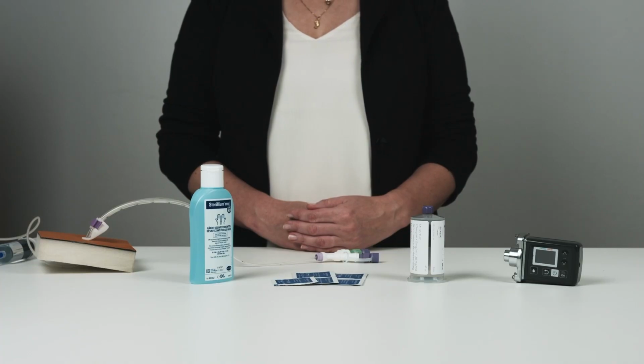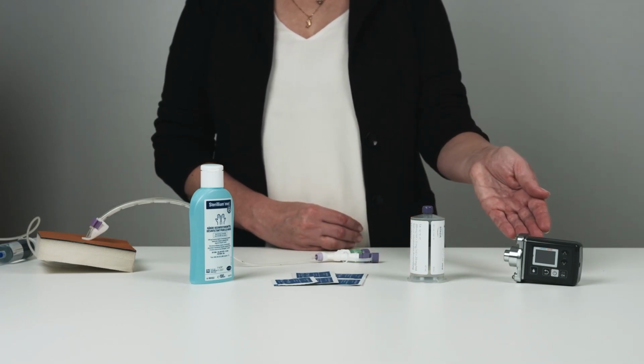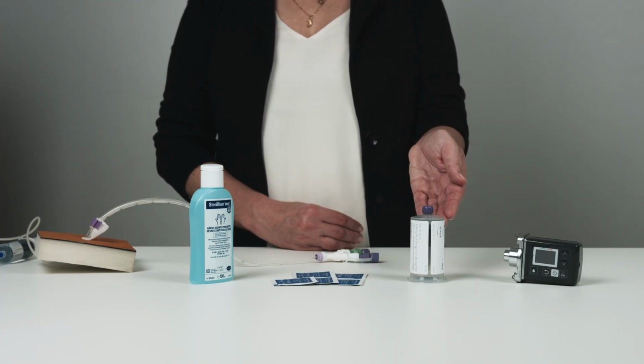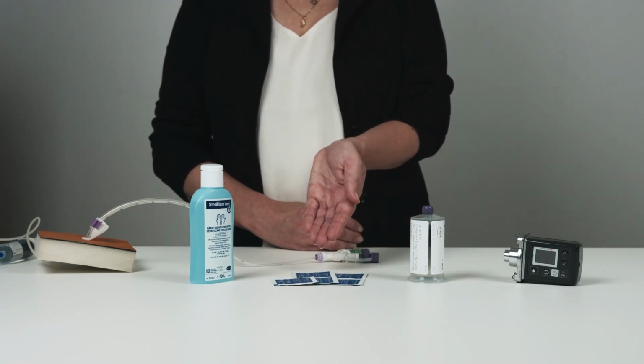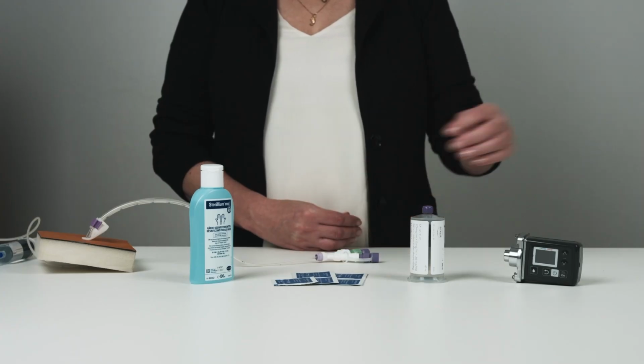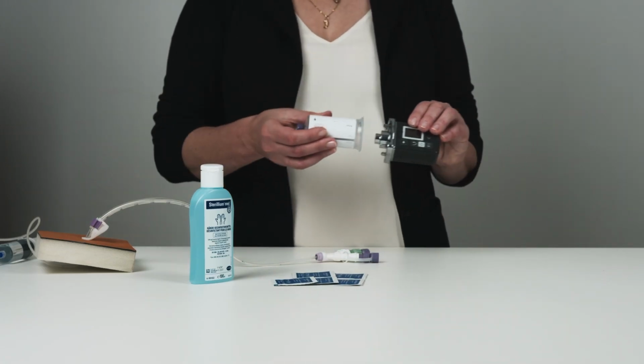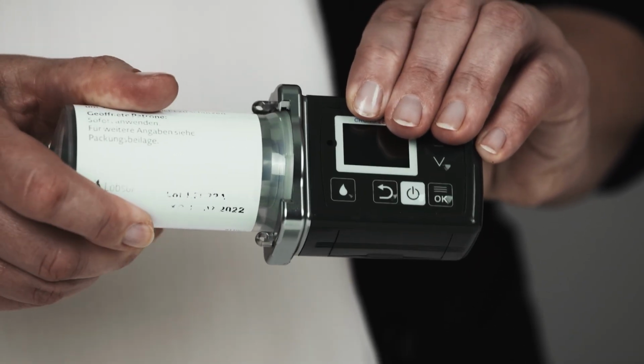To prepare the pump, you will need the Crono LECIG pump, 50 ml cartridge containing 20 mg per milliliter levodopa, 5 mg per milliliter carbidopa, and 20 mg per milliliter entacapone, as well as hand and skin disinfectants. The cartridge needs to be stored in a fridge at 2 to 8 degrees Celsius, protected from light. It can be used for up to 24 hours after removal from the fridge. To prepare the pump, place the cartridge upright onto the pump. Turn the cartridge until it clicks into place.